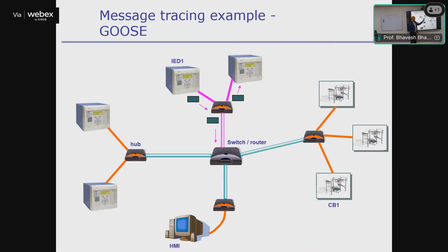It will go through this hub, which has no intelligence, so it's going to send that information everywhere because it can't route - it has no idea where to go. So it will send to this IED, it will send to the switch as well - whatever is connected, it will. This IED will receive it and interpret it, and it knows that it's not for it; the information is actually for circuit breaker 1, so it's going to just ignore that. Then it will go to the switch, and because it's a multicast GOOSE message, there is no information about routing.